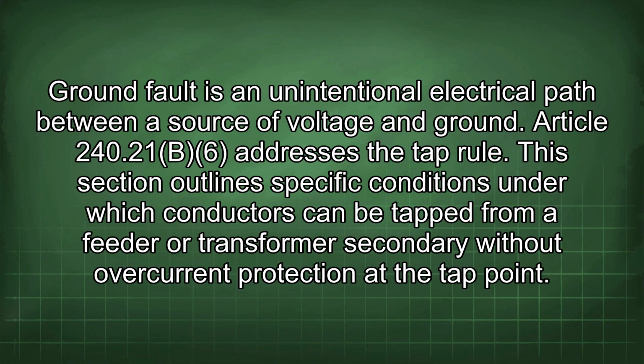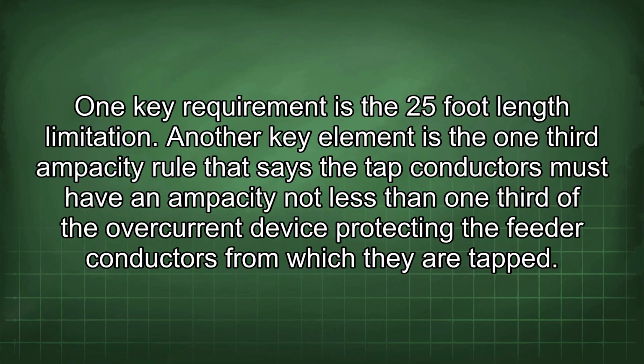240.21(b)(6) addresses the tap rule. This section outlines specific conditions under which conductors can be tapped from a feeder or transformer secondary without overcurrent protection at the tap point. One key requirement is the 25-foot length limitation. Another key element is the 1/3 ampacity rule that says the tap conductors must have an ampacity not less than 1/3 of the overcurrent device protecting the feeder conductors from which they are tapped.